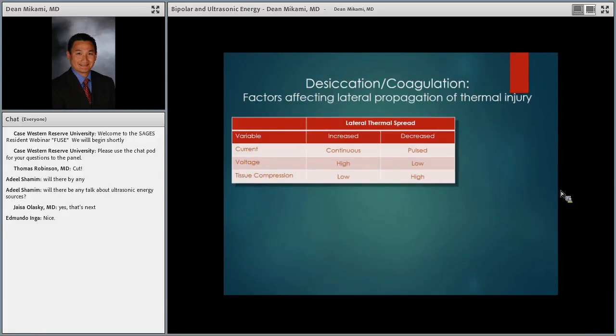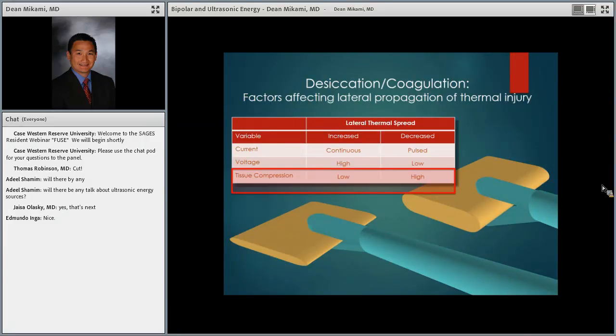So once again, most units now you want high tissue compression. When you close your bipolar instrument, you get a very low voltage and you get a pulse current. What that pulse current does is the ESU of the bipolar machine is actually measuring change in resistance. So when it closes the jaws, it senses back thousands of times a second. It wants to sense what the resistance is, because we know that when we have a good seal, the resistance in the tissue that we're trying to seal goes up significantly, right? So it's looking for a delta change in resistance to complete the seal. And when it hits that delta change in resistance, then you hear those beeps on your machine.